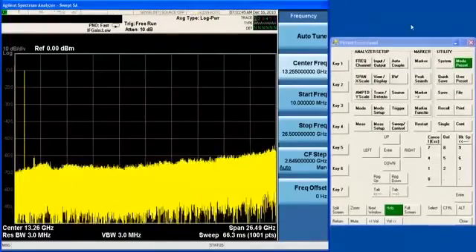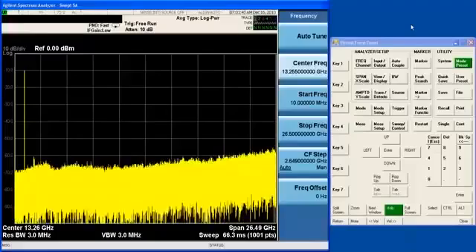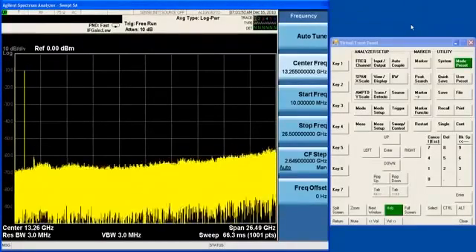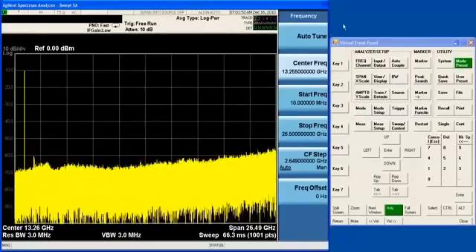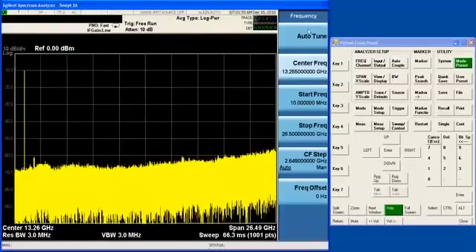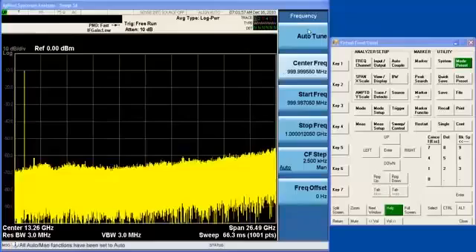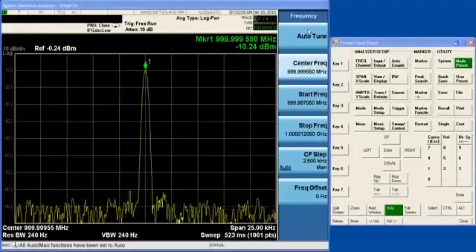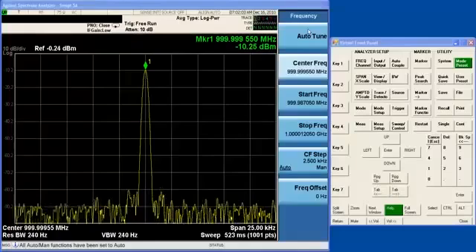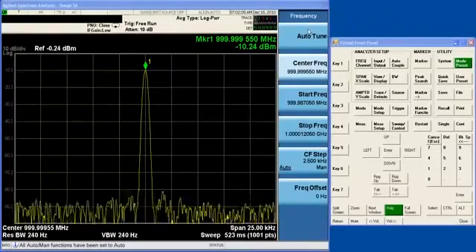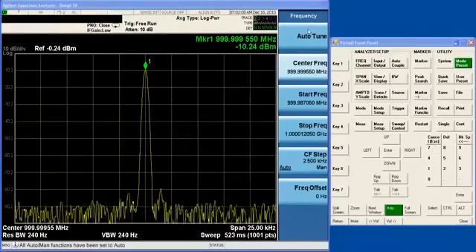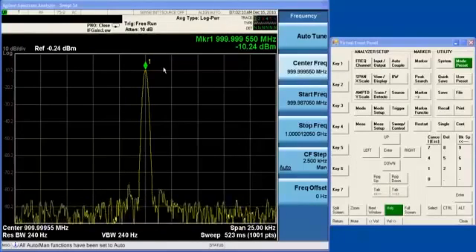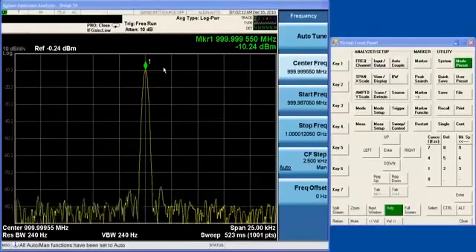Okay, now I am back driving a signal about minus 10 dBm at a GHz into the analyzer. And one of the labor-saving features of the X-Series is this auto-tune functionality that automatically tunes to the strongest signal in the measurement range of the analyzer, sets the span to show the whole signal bandwidth, and sets the reference level so that the signal is 10 dB below the top of the screen.